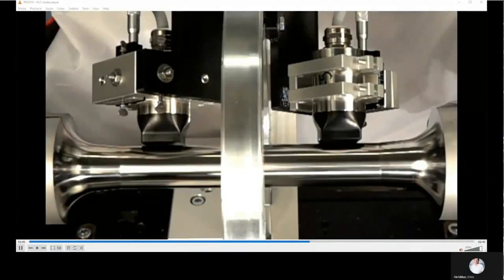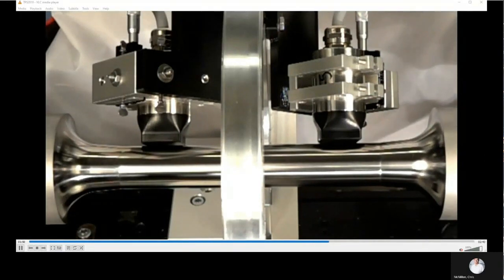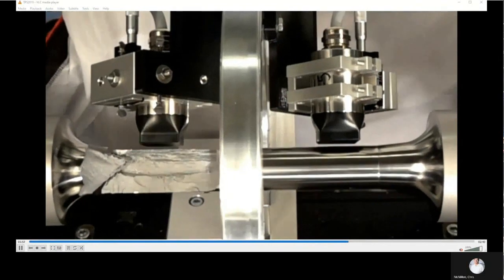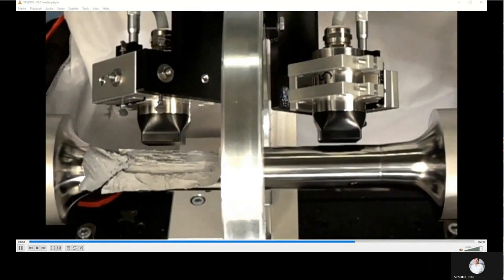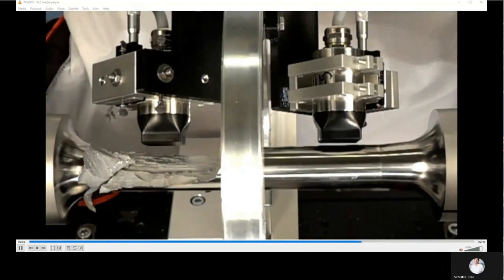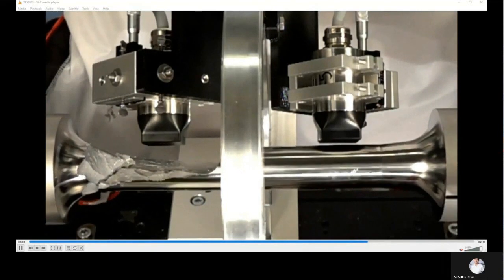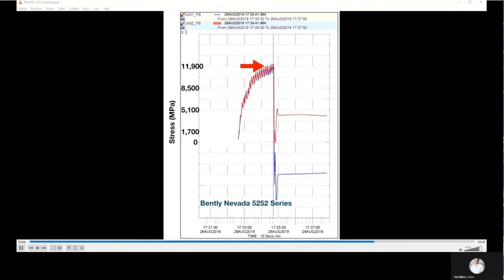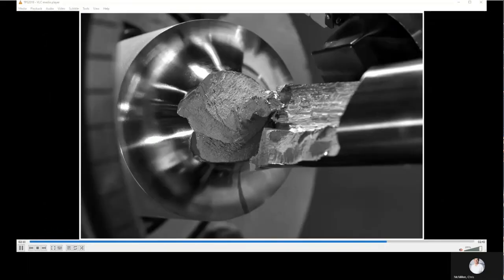Switching to a stationary camera, the scene shows the two probes viewing the test spool. Torque and stress continue to increase. The test specimen fails catastrophically. The 5252 series probes provide continuous monitoring of the shaft up to and through the failure. The shaft failed along lines of plus or minus 45 degrees, consistent with torsional stress.